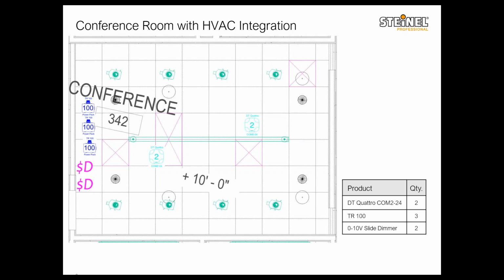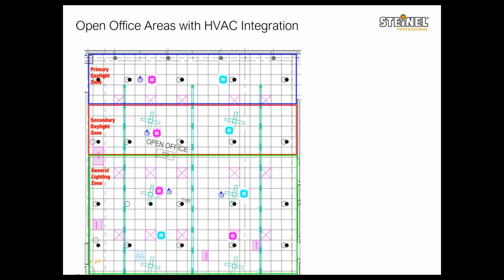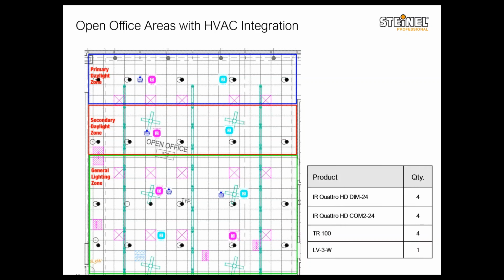So moving on, this would be, well, I want to say a super complicated case that we have here. This is something that you would see in California with Title 24. You have your open office area, your primary daylight zone, your secondary daylight zone, and your general lighting zone. So you would need dimming, daylight responsive control, receptacle control, and now you want to add HVAC integration. So in each zone, you can have your dimming sensor, DIM-24 sensor for dimming and daylight responsive control.